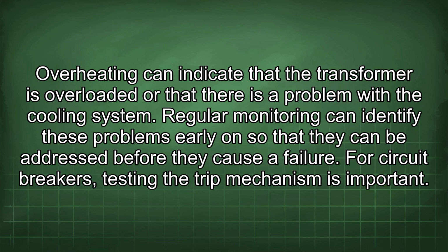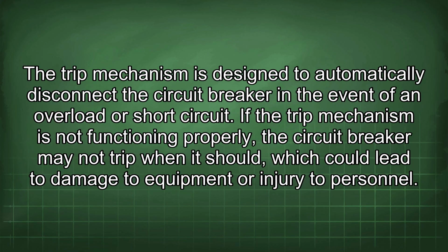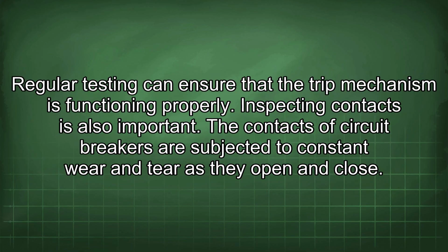For circuit breakers, testing the trip mechanism is important. The trip mechanism is designed to automatically disconnect the circuit breaker in the event of an overload or short circuit. If the trip mechanism is not functioning properly, the circuit breaker may not trip when it should, which could lead to damage to equipment or injury to personnel. Regular testing can ensure that the trip mechanism is functioning properly.